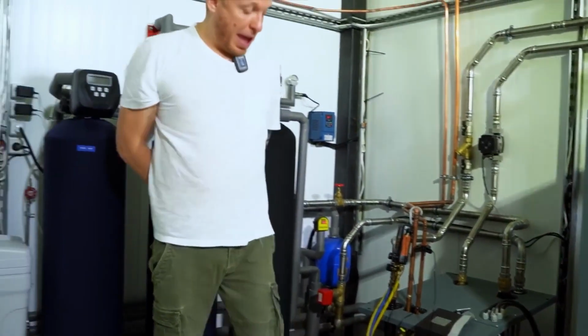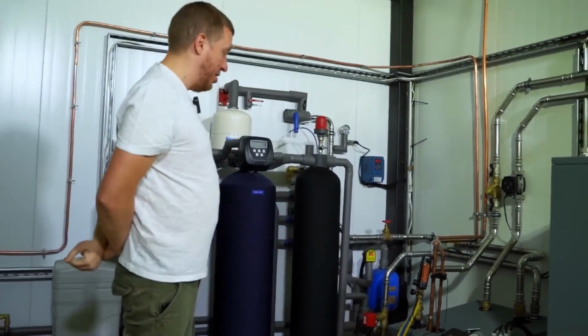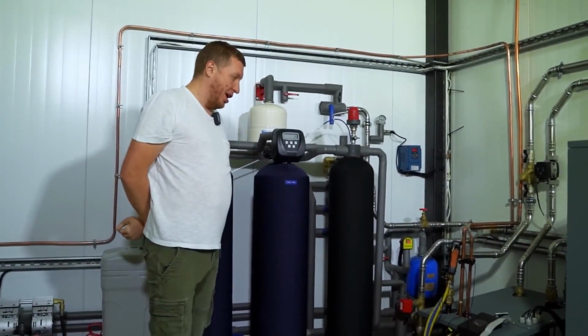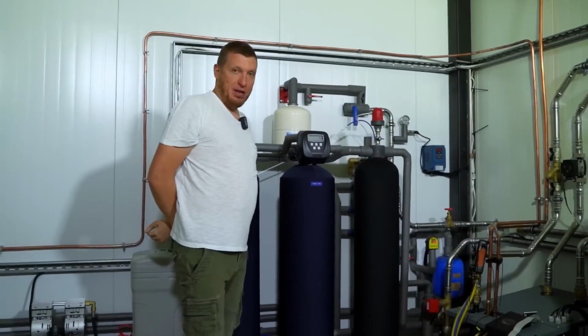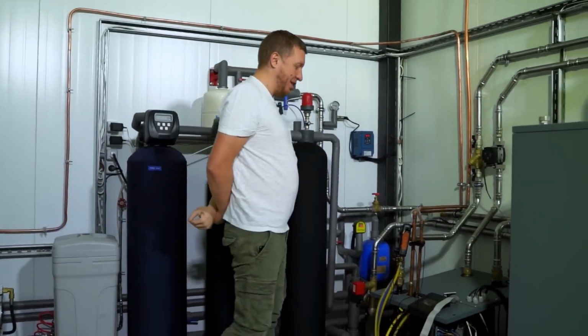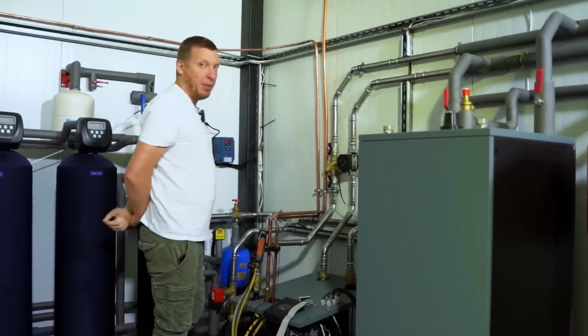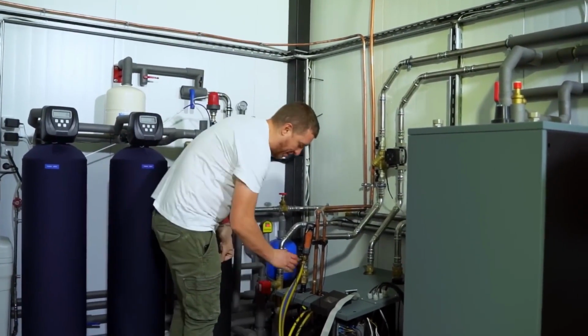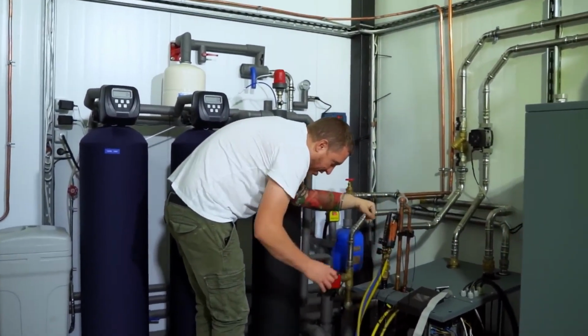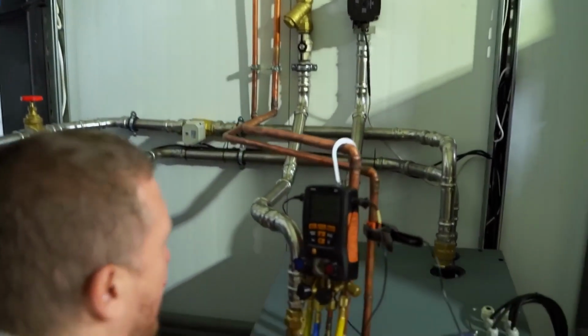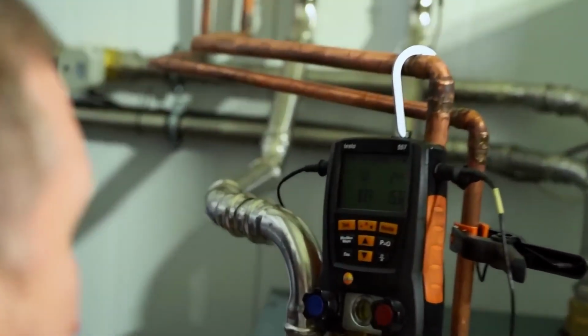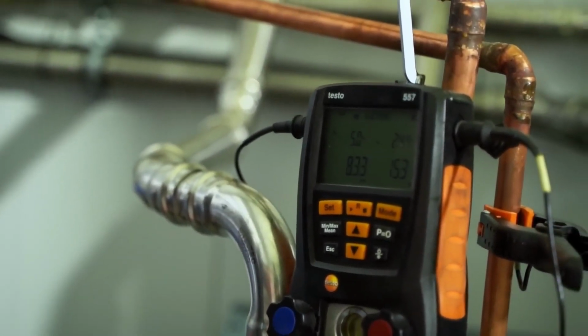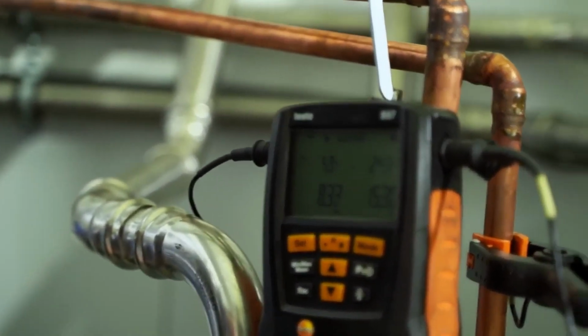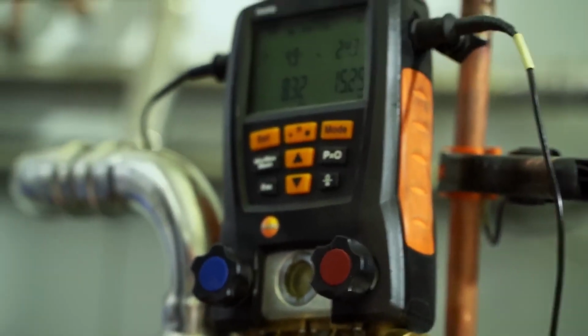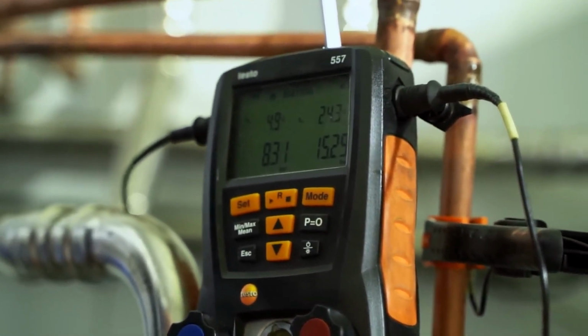Now, we're going to carefully add refrigerant to the running machines in small controlled doses until we clearly see gas subcooling and the superheat is well within its normal operating range. And the evaporation temperature is within normal range. Well, I'll just unscrew it and add it. Right now, it's working just a little from the canister. So we can monitor the T1 reading.